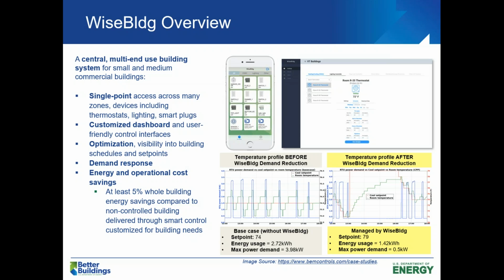Another highlight is on the lower right, a case study that BEM Controls has provided, with the link below the graphic, showing a building owner who wanted to cut peak demand costs. BEM Controls and the WISE Building platform were able to control the set points across the building and widen them during peak demand time, providing the customer with substantial savings.